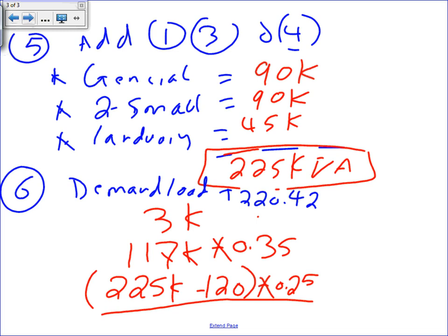Very important, guys. If you guys look at the table, please be on page 64. It will tell you the stuff that we calculated here. You can demand it, means you can cut it down. The reason why we demand, anybody knows why? Highly unlikely that you and all your neighbors are cooking, the air conditioning is fully on, the range is fully on, all the lights are on, all the receptacles are on, the pump is on. No, these are just receptacles. All the lights are on, and you're cooking at the same time, or the kitchen equipment are on at the same time. So it's highly unlikely. Diversity factor, demand factor.